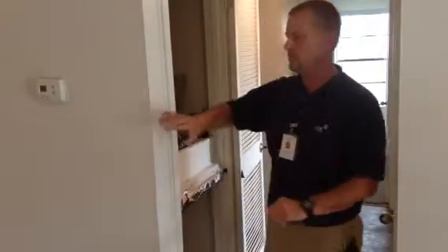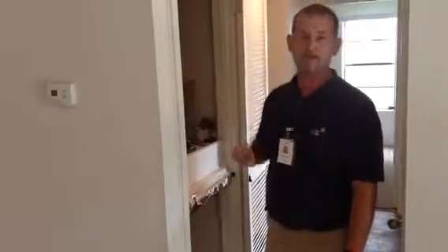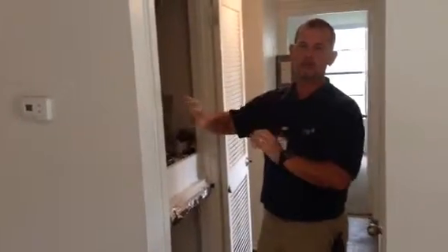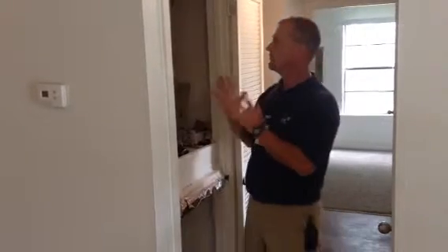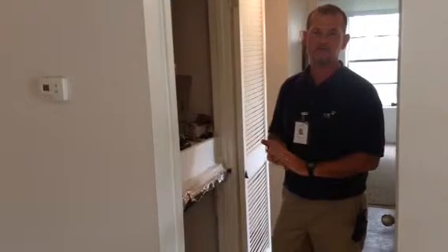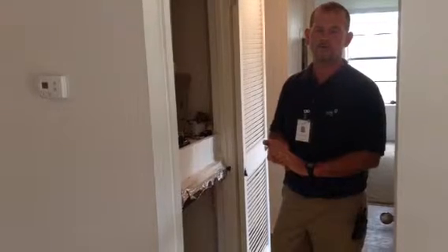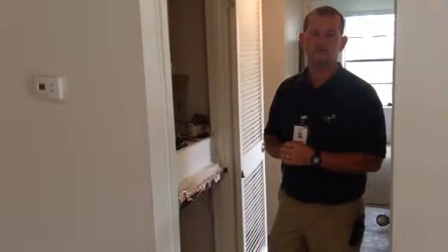Next scenario would be if you have batteries and it's displaying, but the system is not doing anything. You kind of do the same thing, going through the power. It's just going to be a little bit harder to diagnose with the batteries in, because it's going to give you a false sense of something going on. One of the things you definitely want to check is the transformer. If you've got power coming into the air handler, but you don't have 24 volts coming out of the transformer, the transformer is bad.